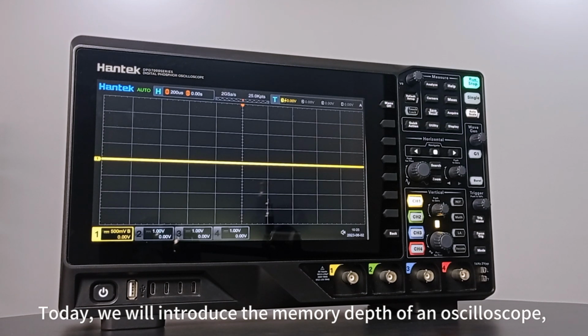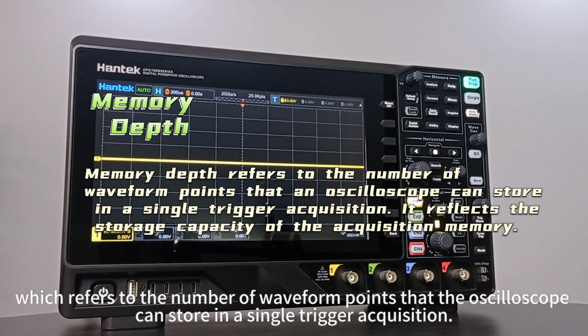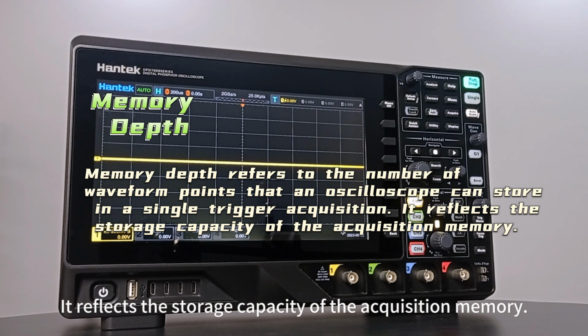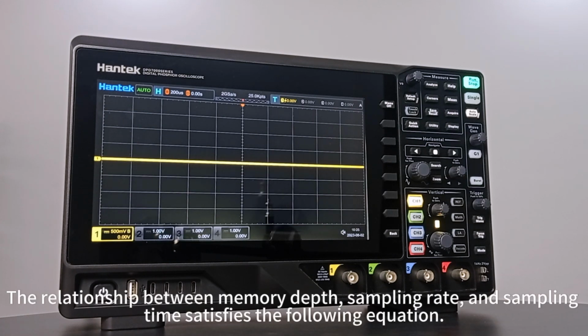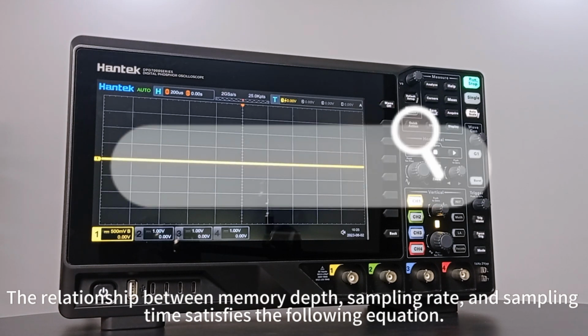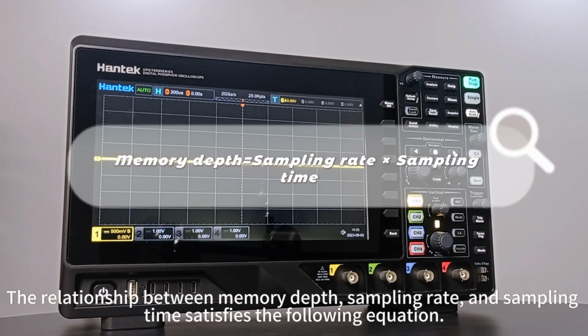Today, we will introduce the memory depth of an oscilloscope, which refers to the number of waveform points that the oscilloscope can store in a single trigger acquisition. It reflects the storage capacity of the acquisition memory. The relationship between memory depth, sampling rate, and sampling time satisfies the following equation.